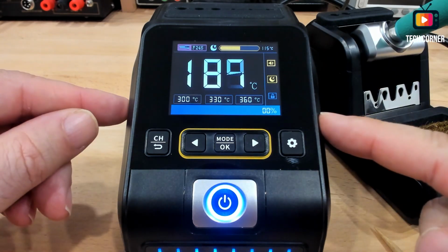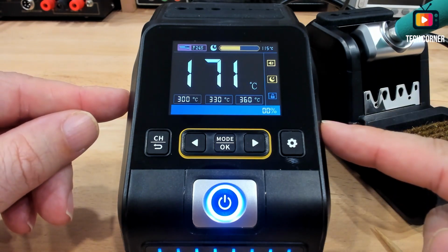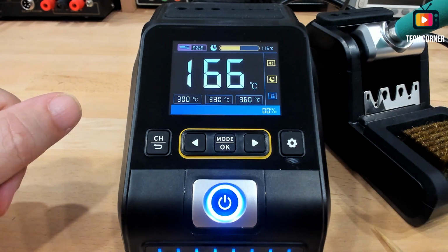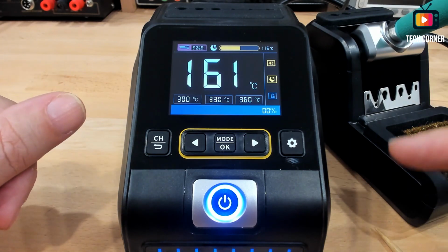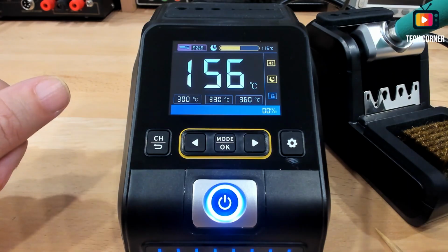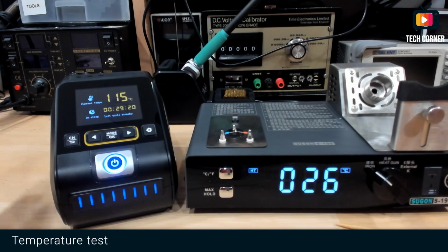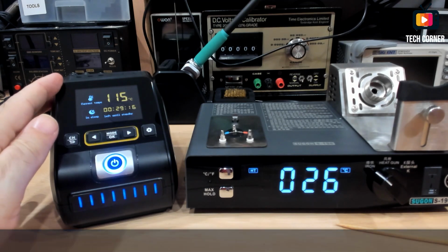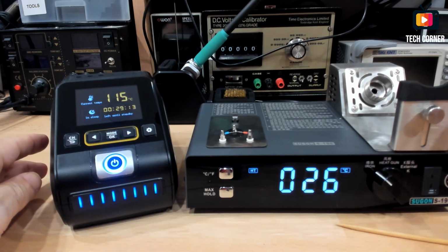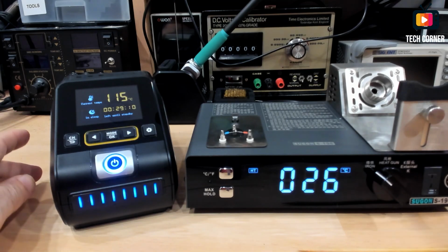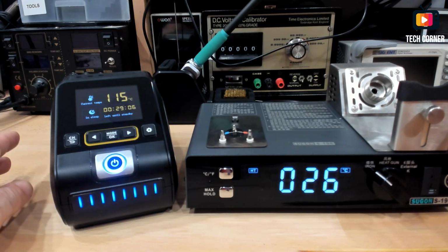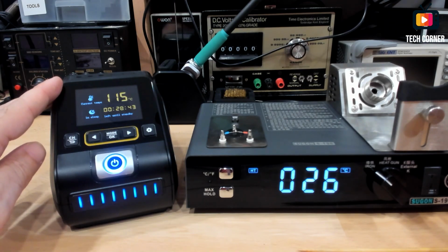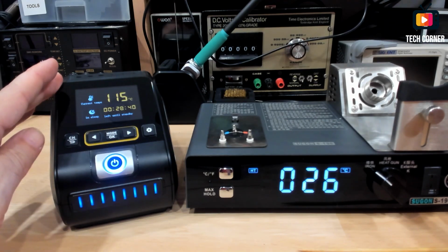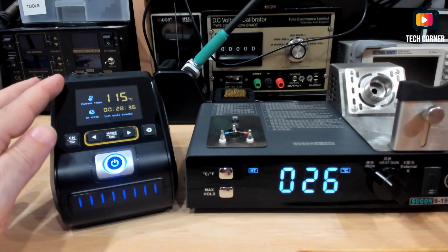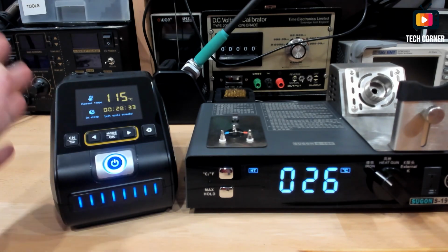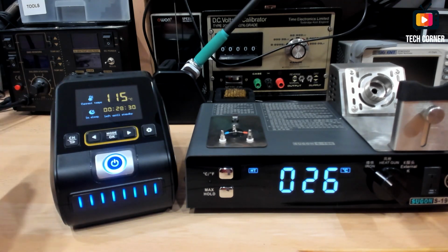What I will do now is do some testing with the temperature thermometer and also the tin test, how many seconds it will take to melt the tin or the solder. Let's move on. For the temperature testing, I have already the DWS-200 on the left side and the S196 from Sugon. That is my temperature tester for soldering stations and also hot air stations. Right now, what I will do is to set the temperature on the DWS-200 to 150 degrees, 250 degrees, and 350 degrees. Why those temperatures? Because those are the temperatures that we use for calibration.